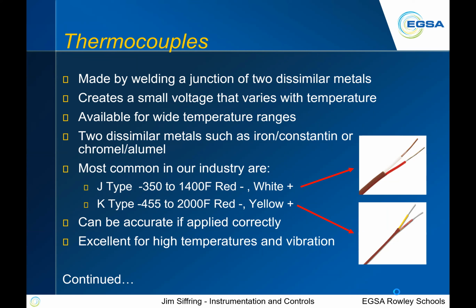But you'll see the colors on there. One wire is red or has red insulation, one wire has white insulation. Those are how you tell what your thermocouple types are. If it's red and yellow, you've got a K type. If it's red and white, you've got a J type. And there's a whole bunch of other types of thermocouples. These are by far the most common in the industry, but you'll see it. And really all you have to do is Google the different types of thermocouple color codes, and it'll tell you what they are.